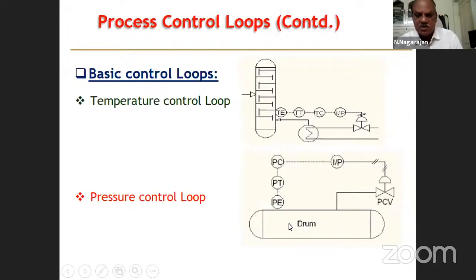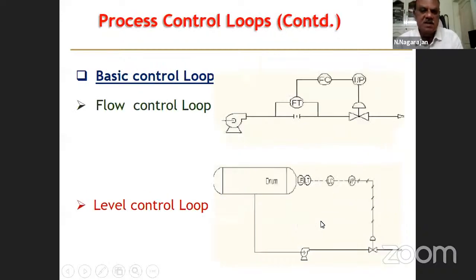So pressure control in a drum, you measure the same, instead of T we have P, pressure element, measuring element, pressure sensor, and then your transmitter. Then from the transmitter the signal goes to the controller, you will have the set point, and then the control action goes to the pressure control valve through the electronic pneumatic converter to open or close the valve according to the pressure to be maintained inside the vessel.